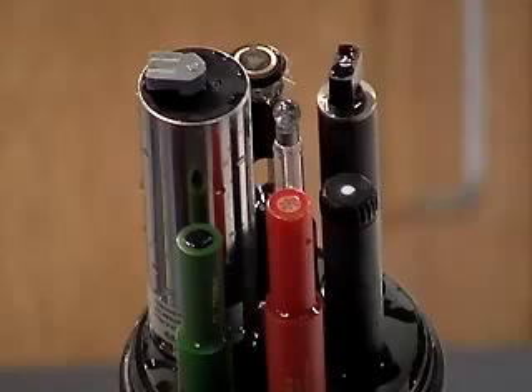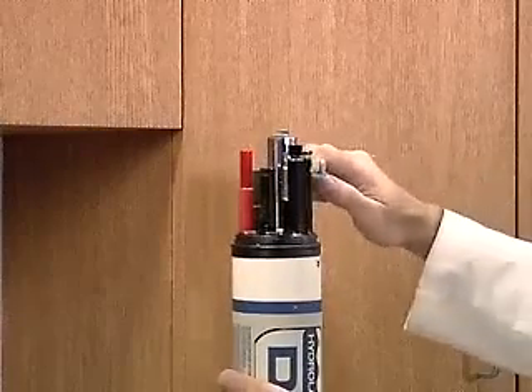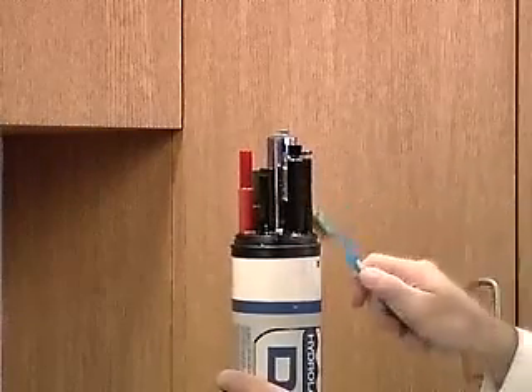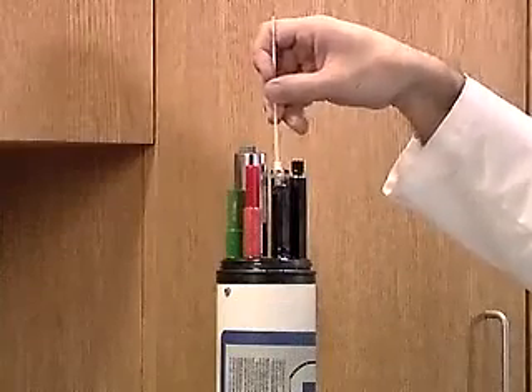Maintenance. In order to give consistently accurate readings, the pH sensor should be maintained on a regular basis. Oils, sediment, and biological contaminants on the bulb or reference junction will result in errant readings or a very slow response. Leaching or dilution of the electrolyte solution in the reference will cause the readings to drift over time. The glass bulb is very thin and fragile. Care should always be taken not to damage it when servicing the instrument. The sensor should be cleaned with a cotton swab or soft brush and soapy water.